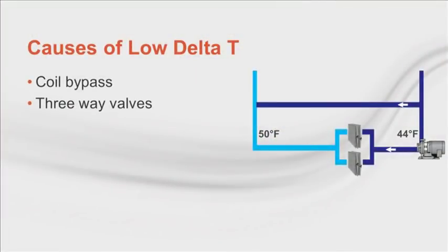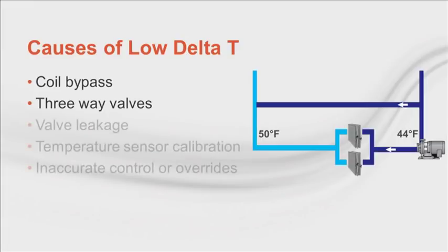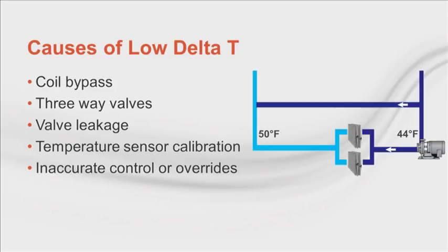Now, these DeltaT criminals also go by the names three-way valve, but two-way valves can also fail to perform. Other reasons include valve leakage, poor calibration, or controls that panic and allow large volumes of water to chase a load that isn't really present. You might also see that valves close to the pump perform differently than valves further out in the loop. Excess pump head prevents the valves from seating properly. Variable speed drives are ideal for preventing excess pump head. However, the pump may be programmed to stay at a higher pressure to keep one or more valves nearly wide open. That's where calibration and inaccurate control come in. If you have a valve that is constantly wide open because the control point it's using is either faulty or out of calibration, you may still see excess pressure even with variable speed pumps.